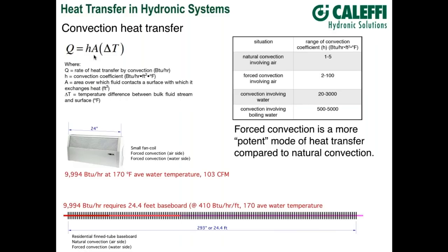Here's a good example in hydronics. That small fan coil up there is two feet wide. Looking at the specs, it'll produce just under 10,000 BTUs per hour with 170°F average water temperature and about 100 CFM airflow. Think about that — 10,000 BTUs per hour with a two-foot-wide heat emitter. To produce that same output with fin tube would require over 24 feet of standard residential fin tube, based on 410 BTUs per hour per foot at 170°F average water temperature.